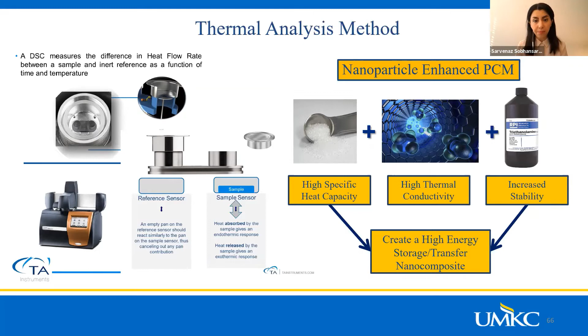The DSC measures the difference in heat flow rate between a sample and an inert reference as a function of time and temperature. The reference sensor needs to use the same pan that we are using on the sample sensor. When heat is absorbed by the sample, it gives an endothermic response, and when heat is released by the sample, it gives an exothermic response. In order to create a material with high heat storage and heat transfer, we again targeted our cheap sugar alcohol sweetener. We integrated nanoparticles with high thermal conductivity into it, and to increase stability and have a uniform mixture, we are adding the dispersant triethanolamine, TEA, to create our nanocomposite.